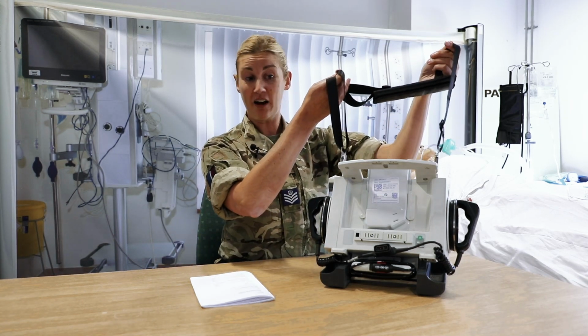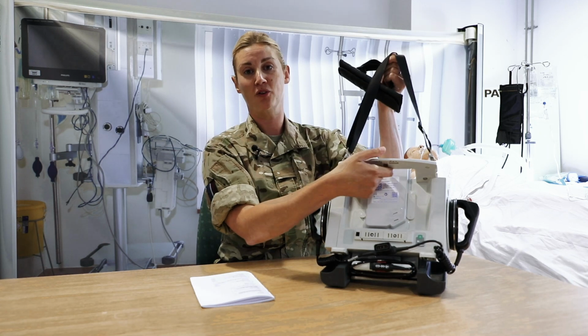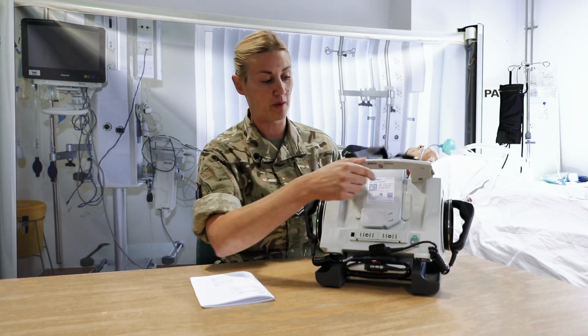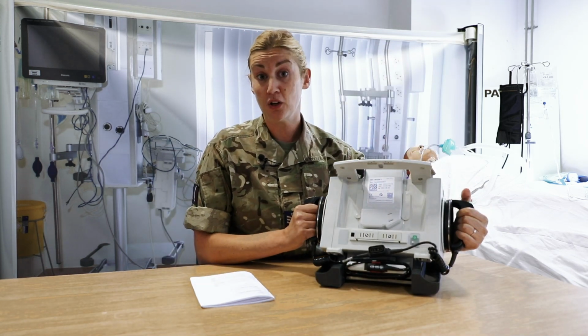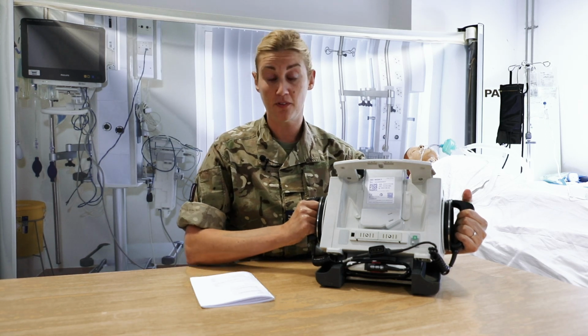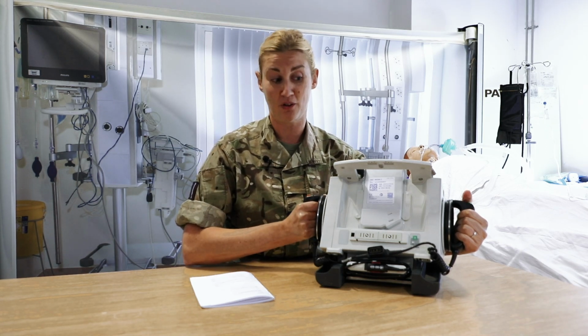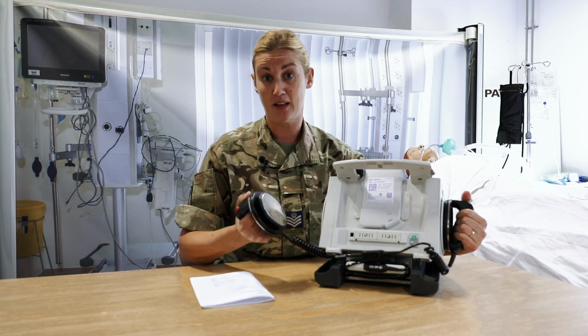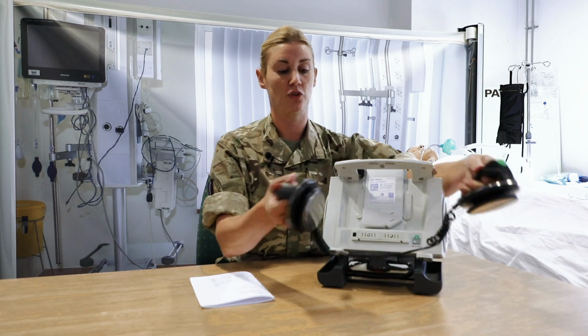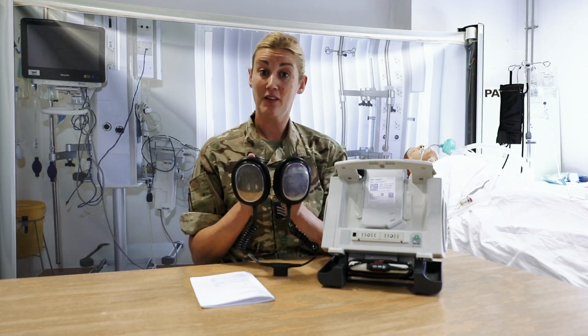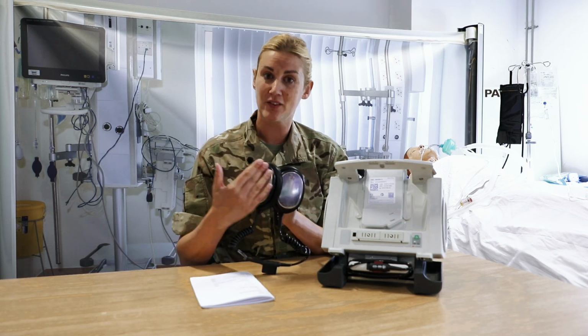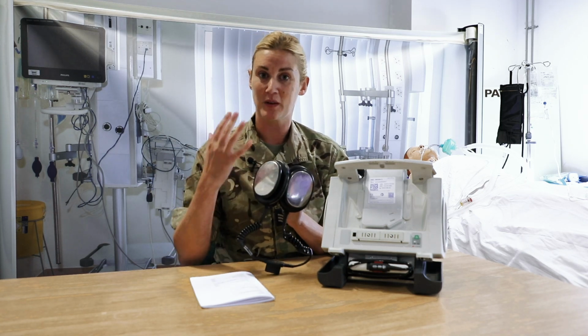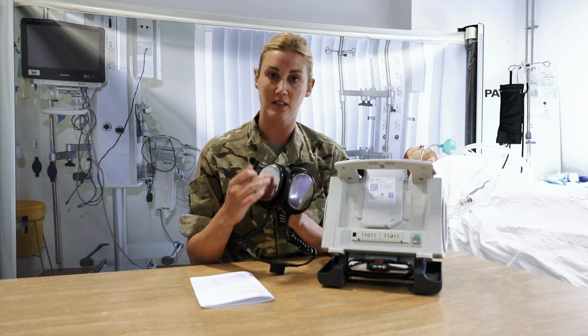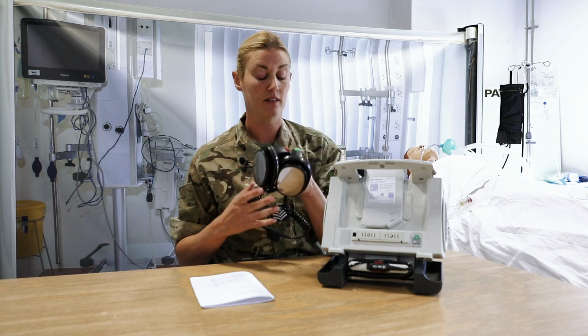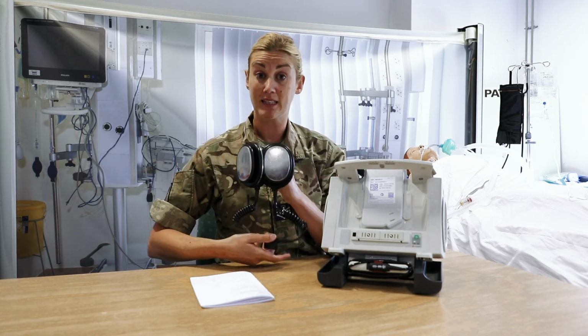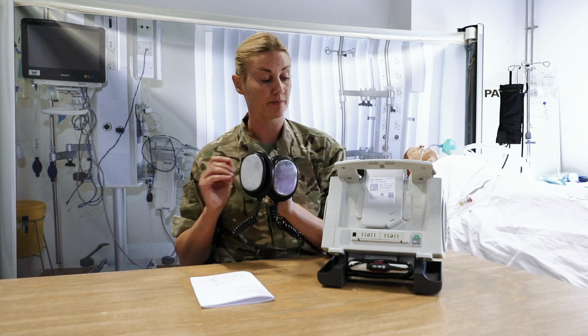You should have a carry handle, and just make sure that if you lift that up, the whole thing doesn't fall apart. And if you are using the paddles, then to remove them, they're a twist towards you if you're facing the defib, and then they will just pull out. So twist them towards you and pull them out. And just give these a look. These are a bit scratched, but make sure they're not really scratched so that you can see bare metal underneath. And make sure that the cable itself looks like it's in good service.